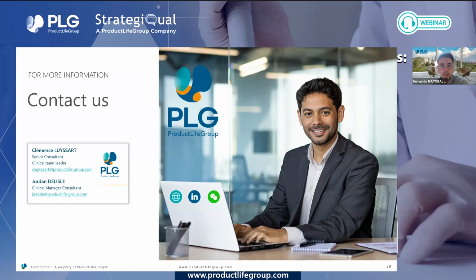Julian is asking, scientific validity can be partly demonstrated with a proof of concept study. Yes. Yes, partly, you said the word. There was a slide where all sources that can be used to demonstrate scientific validity are specified in the IVDR. So a proof of concept study, yes, it's basically a good point to start for scientific validity, because you may prove the link between your analyte and the clinical condition you want to diagnose. So yes.